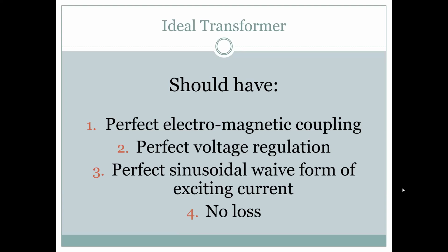Now, a perfect, 100% efficient transformer can be designed if you have perfect electromagnetic coupling, good steel, and perfect voltage regulation. The interesting point is that we try to make the transformer the safest product. When I started my engineering from college to industry, I first stepped in, all the big consultants here, since I'm in Calcutta, had specifications saying the product should be suitable for 6% voltage variation, 3% frequency variation, and 3% combined variation. This was the standardization of all their specifications.